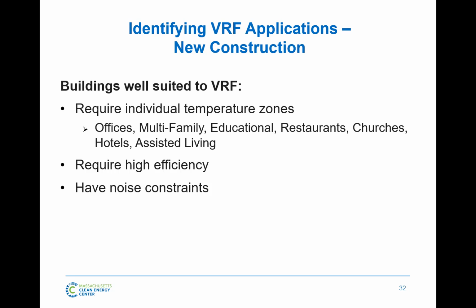requirements. So this is the type of building that's well suited to a zoning system, because it could be the middle of winter, and we could jam this room with this amount of people or double this amount of people, and at some point in the day, we might need cooling, even though the rest of the building doesn't. There's a need for zone control there.